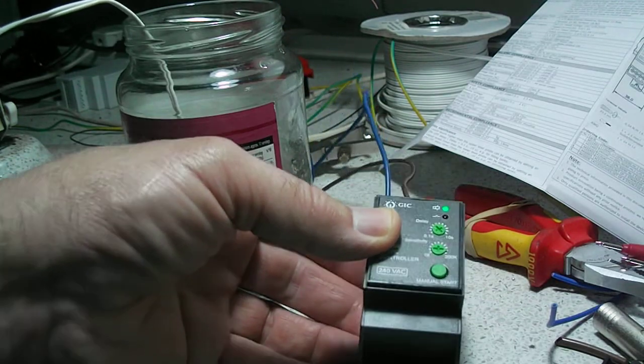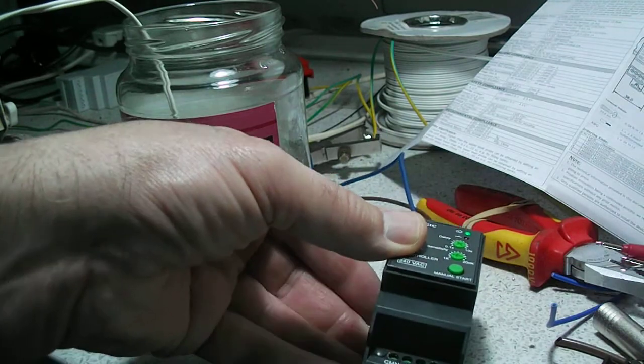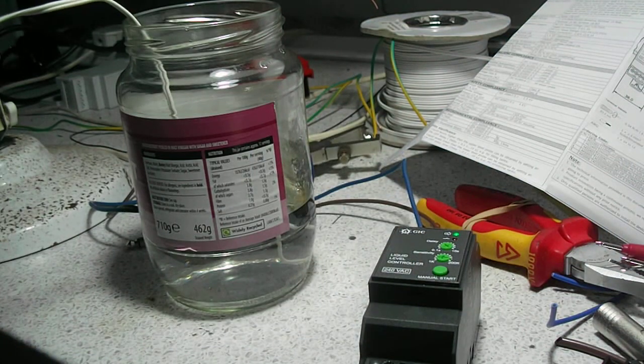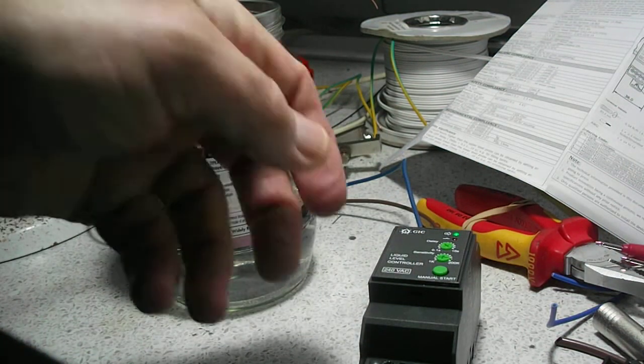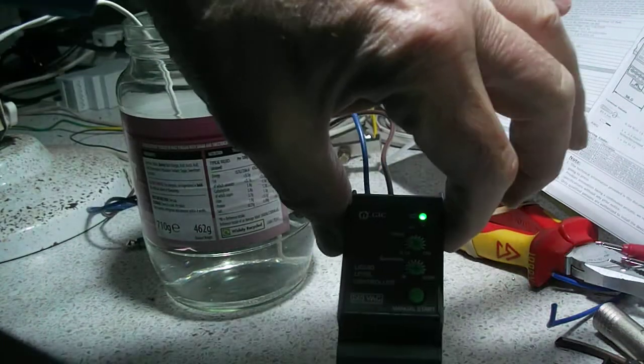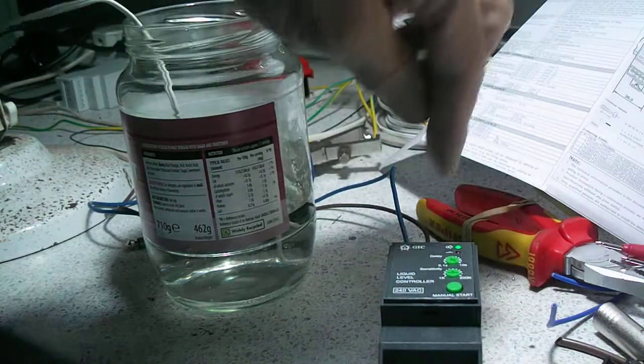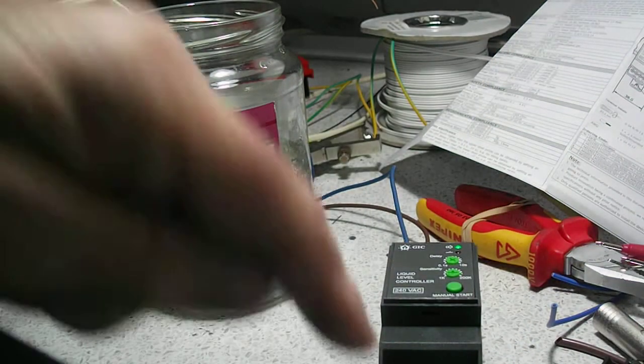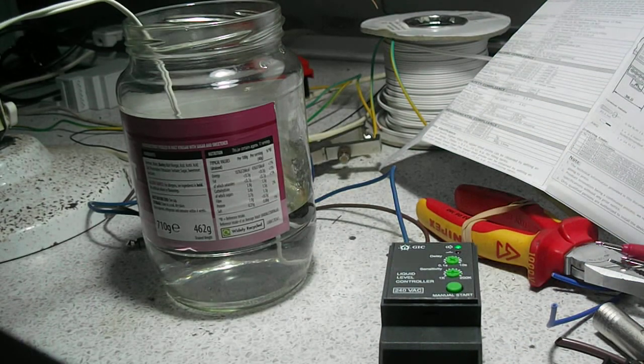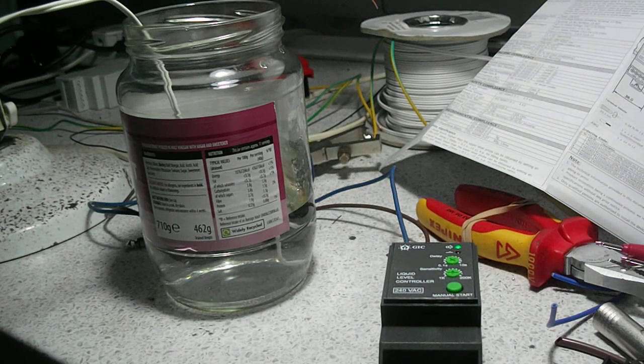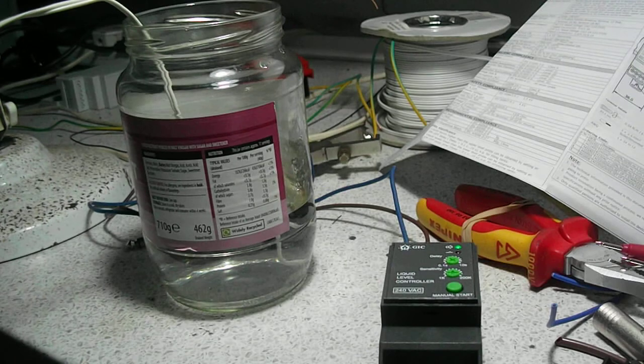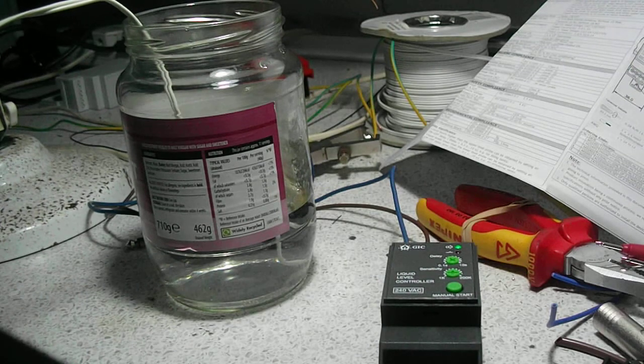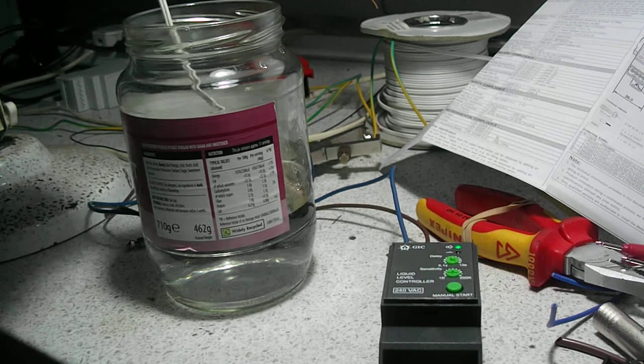It's got quite a high spec, quite a high withstand voltage from the input at 230 volts to the output. In fact, the output voltage across the sensor leads is only about 2 volts and it's AC to reduce the electrolytic effect across the electrodes.